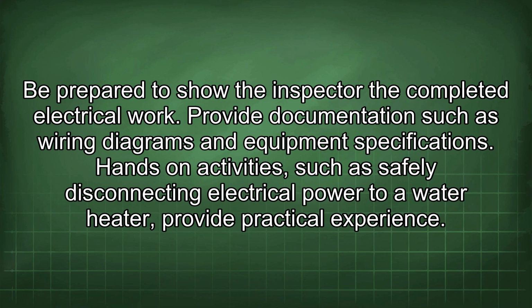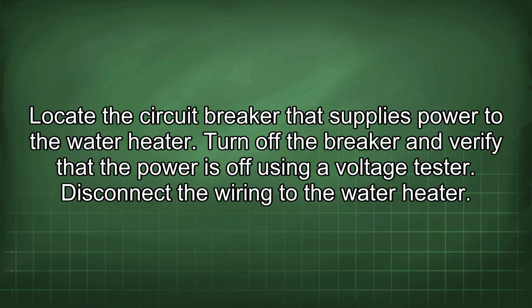Hands-on activities, such as safely disconnecting electrical power to a water heater, provide practical experience. Locate the circuit breaker that supplies power to the water heater. Turn off the breaker and verify that the power is off using a voltage tester. Disconnect the wiring to the water heater.